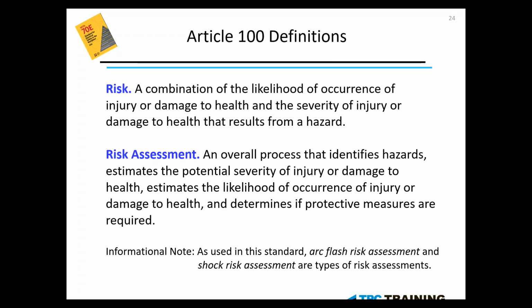Moving along, the definition of risk is a combination of likelihood of occurrence of injury or damage to health and the severity of injury and damage to health. I bring this up because this code book is bringing this conversation to the forefront. In addition to other requirements, it is the assessments. The assessments are becoming more and more stringent, and they're incorporating such things as an arc flash risk assessment and the shock risk assessment, as you see on the slide. This, in a short conversation here, is just a requirement along with the labels and so on, but it is actually a very large conversation. But real quick, it is the likelihood.